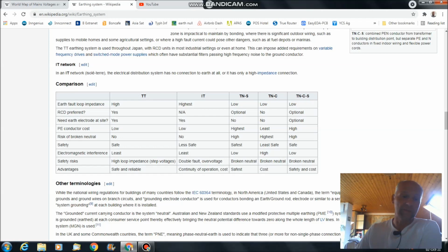You can see here in advantages, you will see continuity of operation. So the IT system in many cases is used in industrial installations where big machines are supplied by isolation transformers, and where it is critical that those machines actually do not stop when there is a fault. So these are really special cases where IT systems have big advantages, and there they are used, but not in home installations. That's why we have to choose one of the 4 earthing systems which really do use a connection towards earth to provide a return path for fault currents. This is the reason why this is actually done.